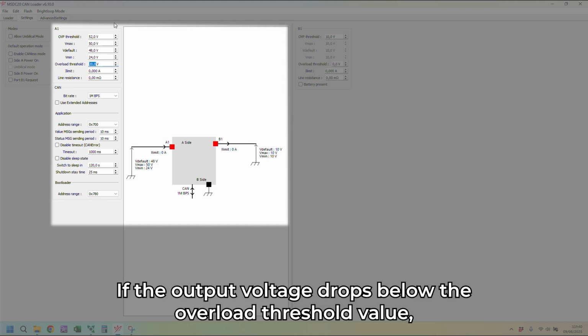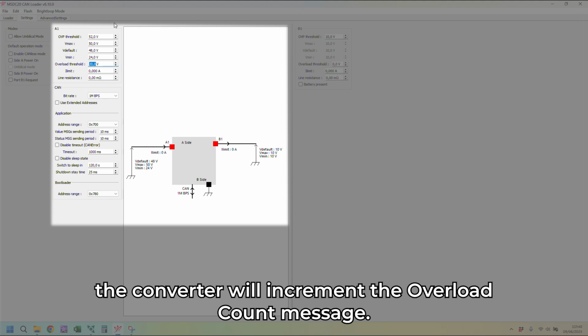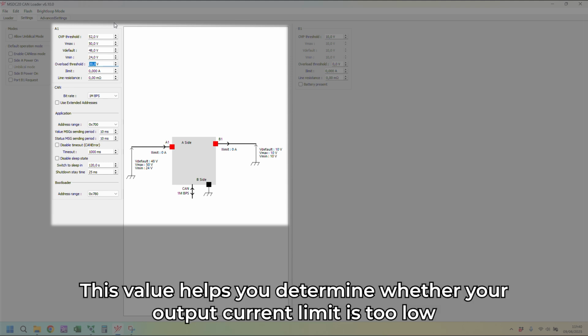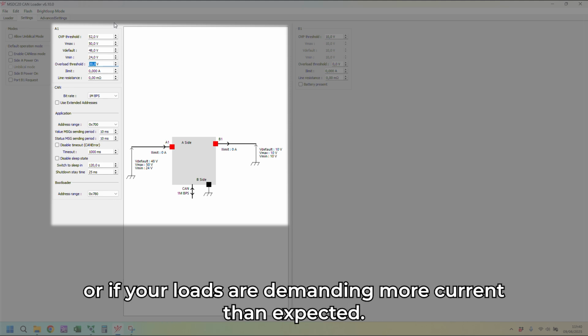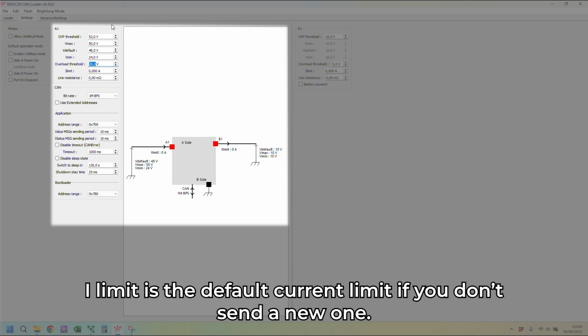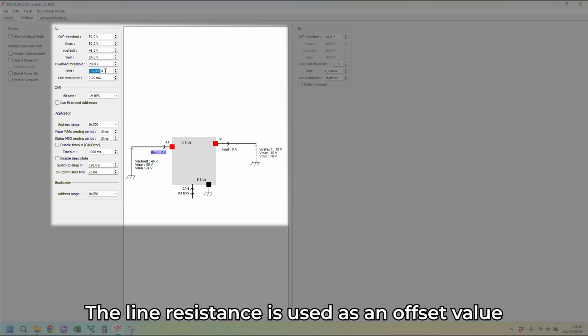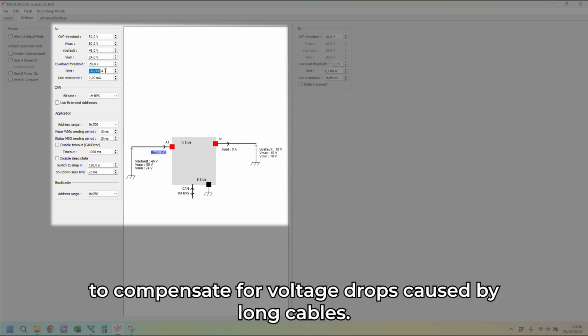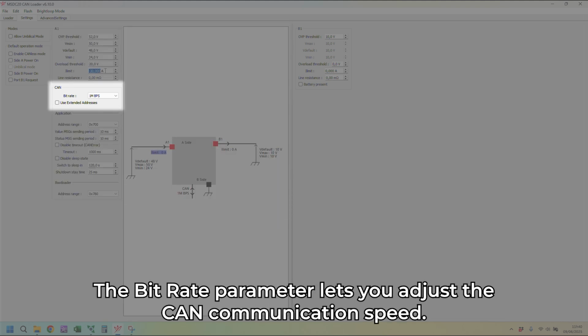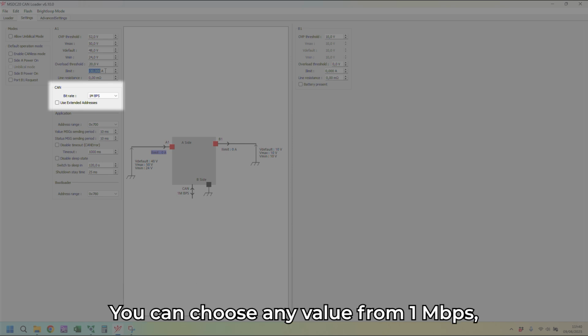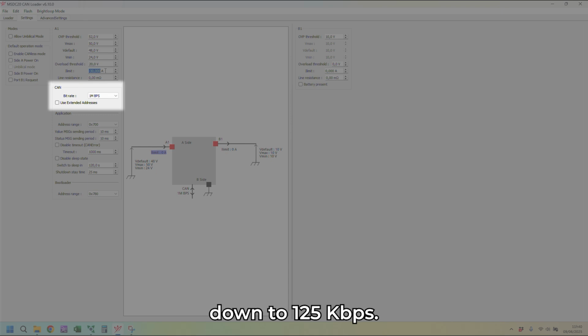If the output voltage drops below the overload threshold value, the converter will increment the overload count message. This value helps you determine whether your output current limit is too low or if your loads are demanding more current than expected. I-limit is the default current limit if you don't send a new one. The line resistance is used as an offset value to compensate for voltage drops caused by long cables. The bitrate parameter lets you adjust the CAN communication speed. You can choose any value from 1 megabit per second down to 125 kilobits per second.